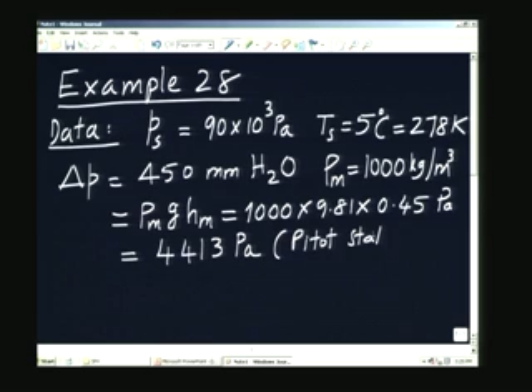So, we can calculate the delta P in SI units by taking it as rho m g h m. So, this will be 1000 multiplied by 9.81 multiplied by 450 millimeters, which will be 0.45 meters of water column. So, this will be in pascals, and if you calculate the value, it comes to 4413 pascals. That is the pressure developed by the pitot-static tube. So, this is the pitot-static pressure difference.